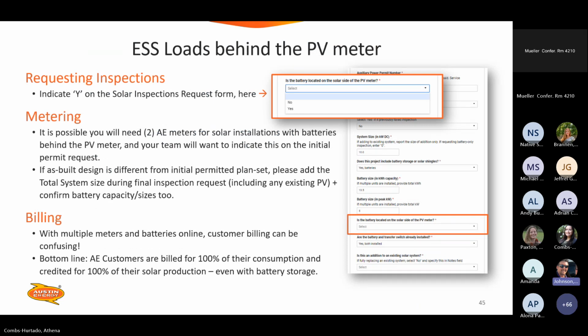All right, requesting inspections, indicate yes on the solar inspection request form here: yes, the battery is located on the solar side of the PV meter, or no if not appropriate. Metering. It is possible you will need 2 AE meters for solar installations with batteries behind the PV meter, and your team will want to indicate this on the initial permit request. If the as-built design is different from the initial permit plan set, please add the total system size during the final inspection request. With multiple meters and batteries online, customer billing can become confusing. Bottom line, AE customers are billed for 100% of their consumption and credited for 100% of their solar production, even with battery storage. This is why at final inspection, we are testing full functionality to make sure that the billing in the end is as accurate as possible. Next slide.